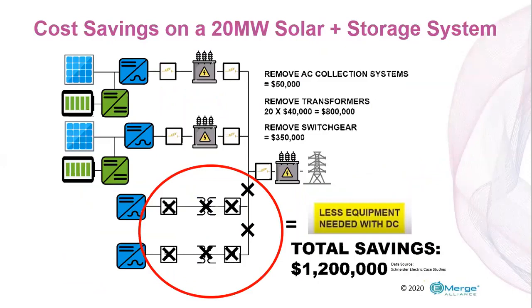I know we reviewed the material that Schneider Electric had, and they indicated in one of their cases, a 20 megawatt solar storage system, there were significant savings in equipment when they went to the DC coupled buses. This again was in a fairly large system. By eliminating some of the switchgear, and also reducing the count of transformers and things, they were actually able to save a fairly generous amount of money.